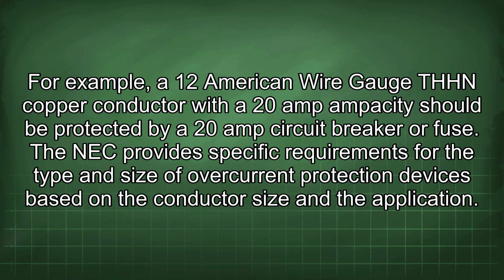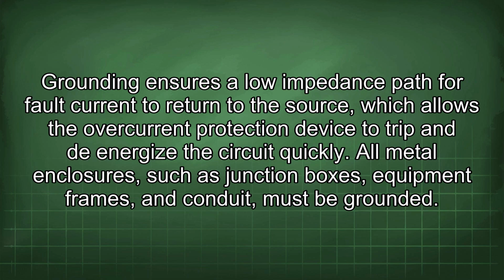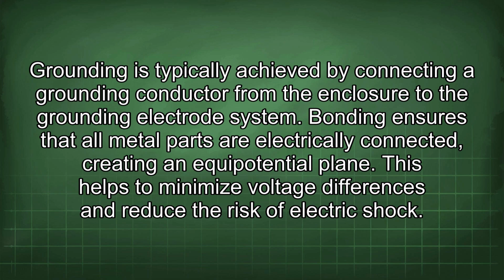Grounding ensures a low impedance path for fault current to return to the source, which allows the overcurrent protection device to trip and de-energize the circuit quickly. All metal enclosures, such as junction boxes, equipment frames, and conduit, must be grounded. Grounding is typically achieved by connecting a grounding conductor from the enclosure to the grounding electrode system.